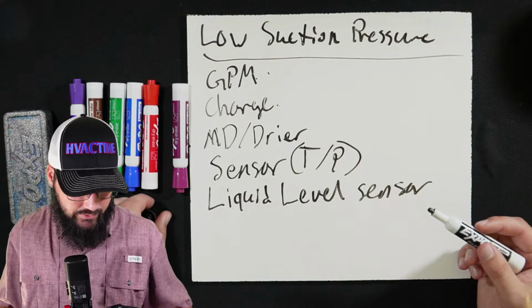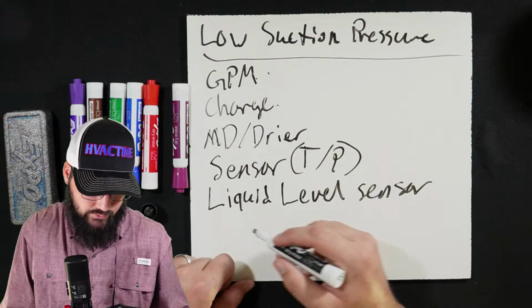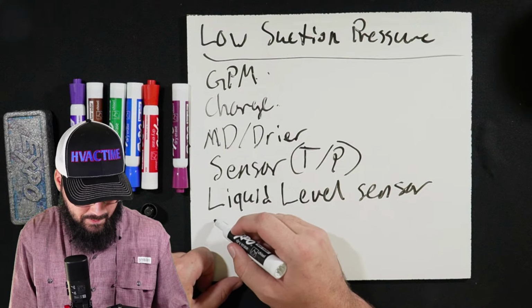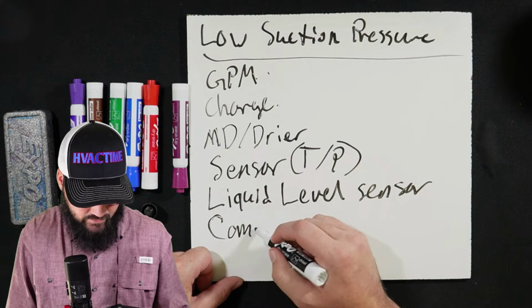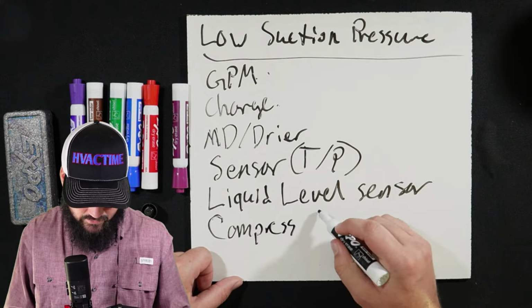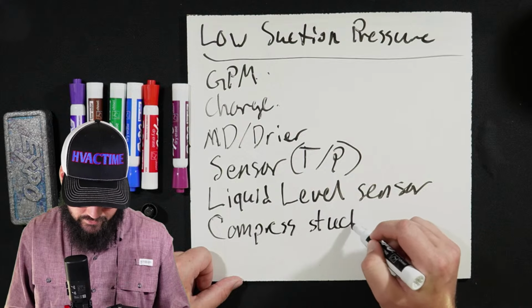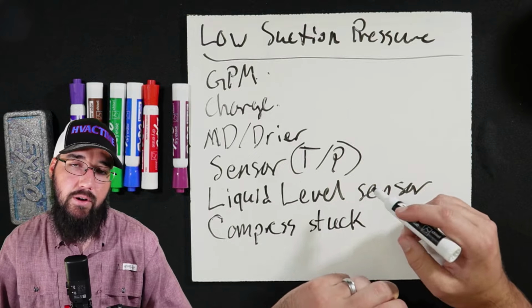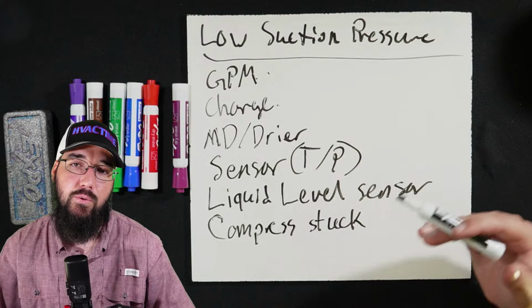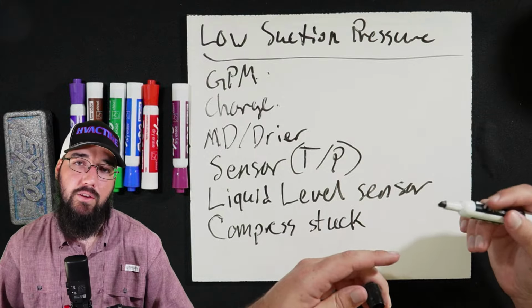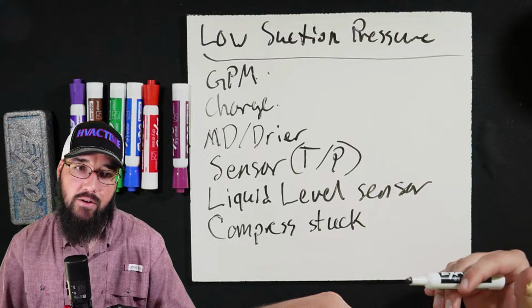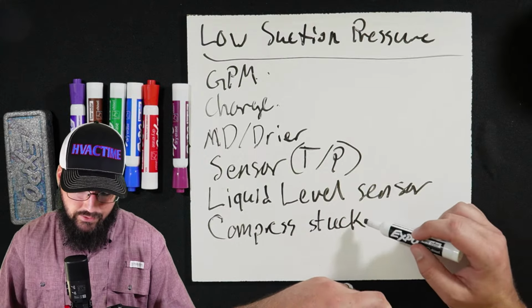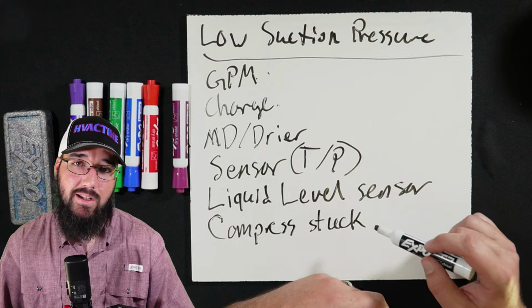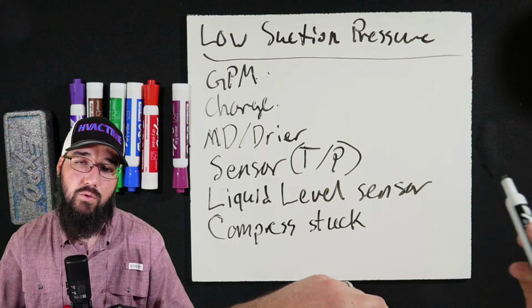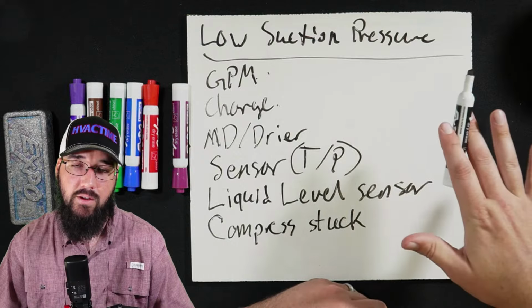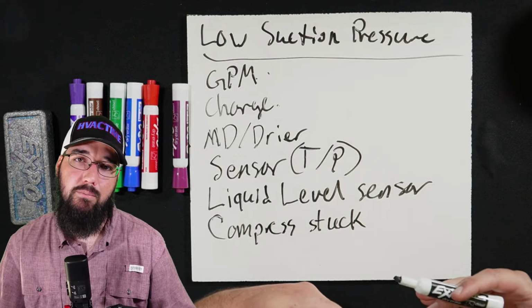Maybe the machine is getting stuck in a loaded position. Okay, so is the compressor unloading? We'll say compressor stuck. Okay, so there's a slide valve in that compressor. Is that compressor able to unload itself? Do you see the RLA fluctuating? Is it coming down to make leaving water set point? Thing is, if you're seeing this, what you will likely see is the leaving water is also going to be lower than set point significantly, and you're not going to see the compressor backing off.